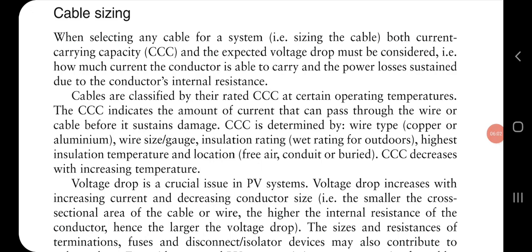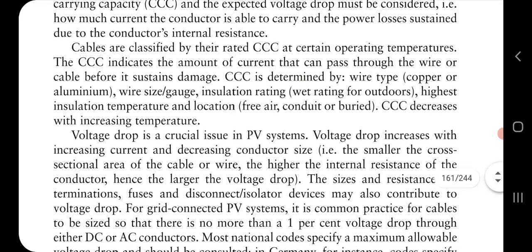Cable size plays a very important role. We have to select the cable size in such a way that it should not have too much voltage drop. So current carrying capacity, that is called CCC. The CCC has two things: one is the power loss and the voltage drop due to the internal resistance. And it operates at certain temperatures, so the amount of current which is passing through it will affect this a lot.